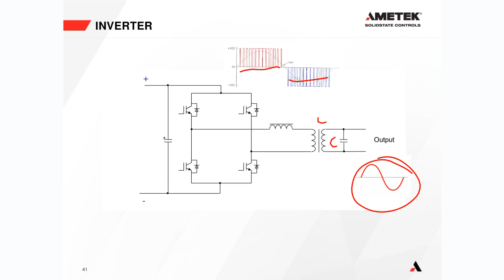Yes and no, that's a very good question. A transformer is an inductor or reactor, so it does have inductor properties, meaning yes, it is smoothing. On this older drawing, we used to have a separate inductor and a separate winding for the transformer. Now we've designed our transformer so the inductance is built into the primary and secondary windings, giving us the action of a reactor. So basically we have an LC circuit filtering out the harmonics of the pulse width modulated waveform and turning it into this synthesized AC waveform. That reactance or inductance inside is a choke.